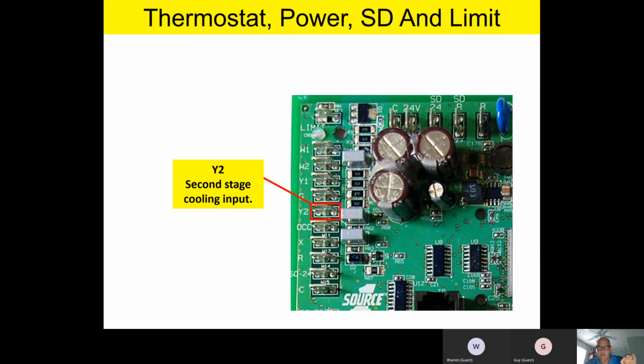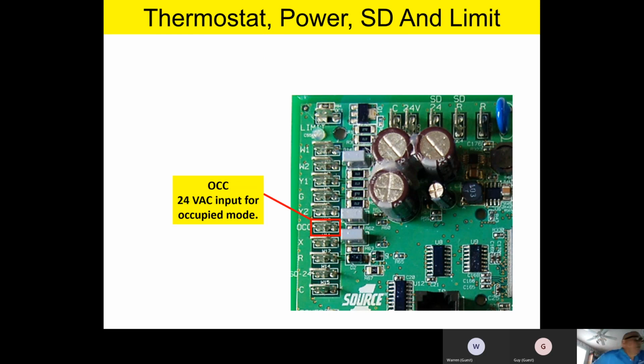Now, this is where we start getting a little bit unique in the fact that it's just some of the features of our Champion control board. The OCC is a 24 volt input for occupied mode. So if you have a thermostat that has the capability of occupied, unoccupied mode, you can utilize this to tell the board it's occupied or unoccupied. If you do not use this circuitry, this is just a little field tip, and you're on a conventional thermostat, what I like to have contractors do is put a permanent jumper between OCC and R, 24 volt hot. And what that does, when you put a permanent jumper between OCC and R, 24 volt hot, it tells the board, or it kind of tricks the board into thinking it's occupied all the time.